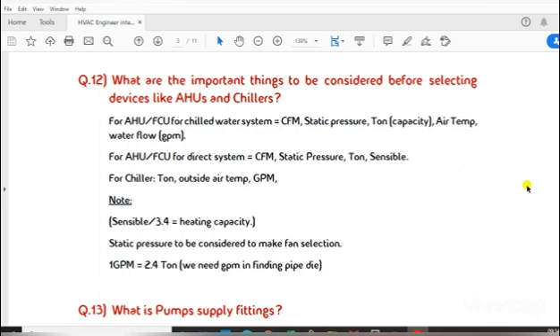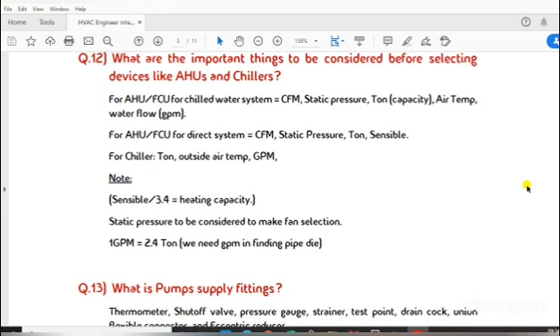For AHU/FCU for direct system: CFM, static pressure, ton sensible. For chiller: ton, outside air temperature, GPM. Note: sensible 3.4 equals heating capacity. Static pressure to be considered to make fan selection. 1 GPM equals 2.4 ton, we need GPM in finding pipe die.